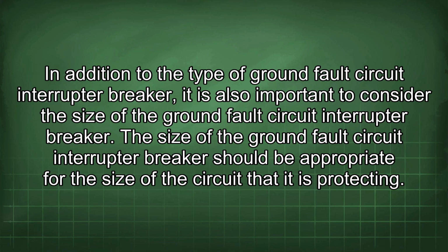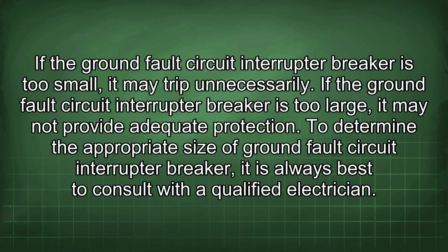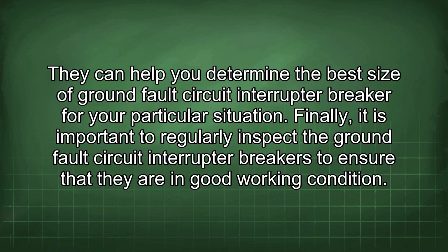In addition to the type of ground fault circuit interrupter breaker, it is also important to consider the size of the ground fault circuit interrupter breaker. The size should be appropriate for the size of the circuit that it is protecting. If the ground fault circuit interrupter breaker is too small, it may trip unnecessarily. If it is too large, it may not provide adequate protection. To determine the appropriate size, it is always best to consult with a qualified electrician. They can help you determine the best size of ground fault circuit interrupter breaker for your particular situation.